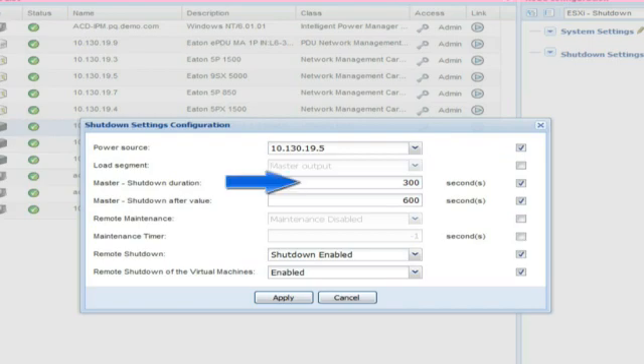Master Shutdown Duration: Enter an amount of time in seconds which will dictate the length of time the host will have to complete its entire shutdown. The virtual machines will shut down first and then the host. Once the designated time expires, the UPS load segment will de-energize.